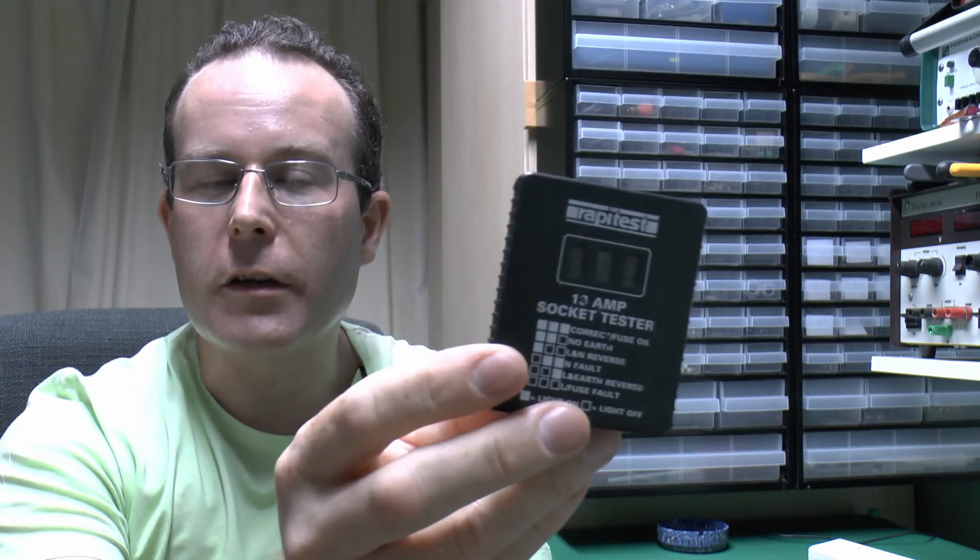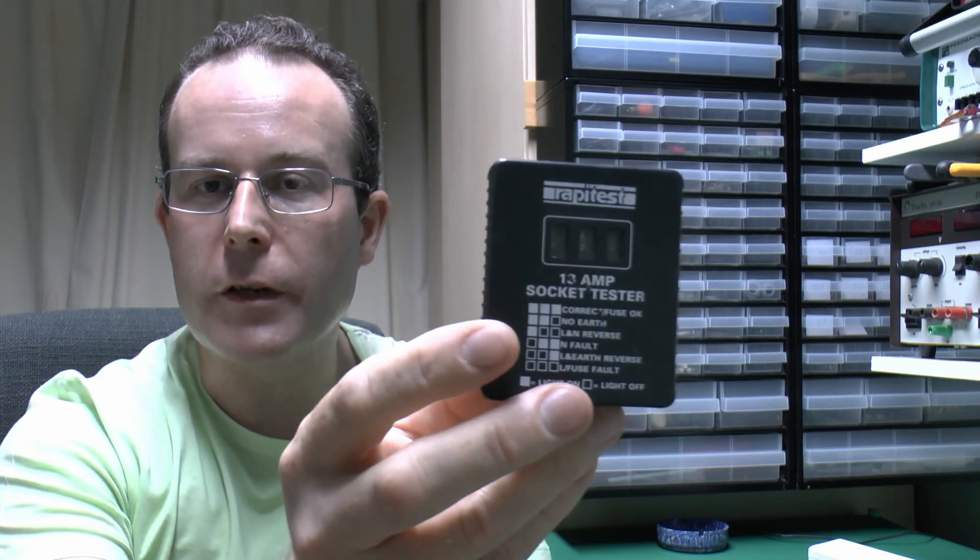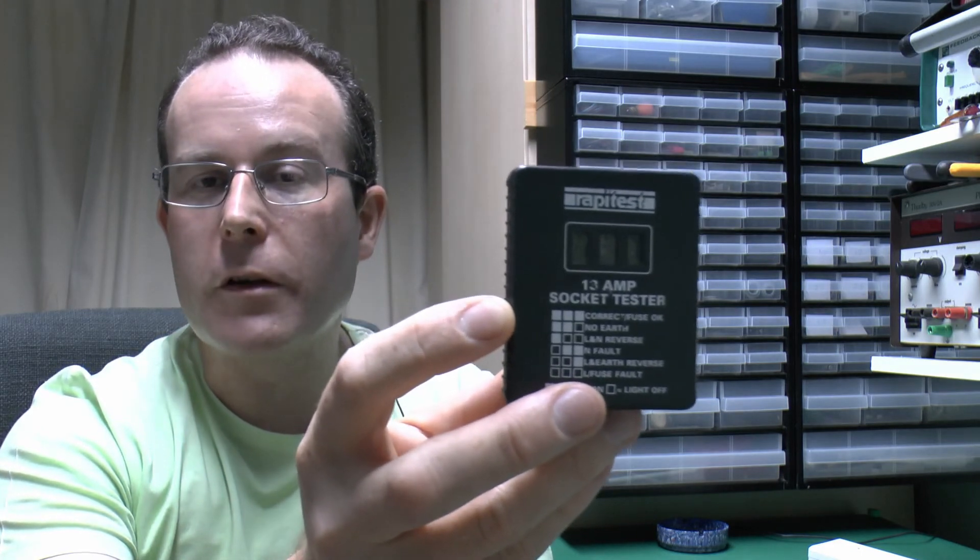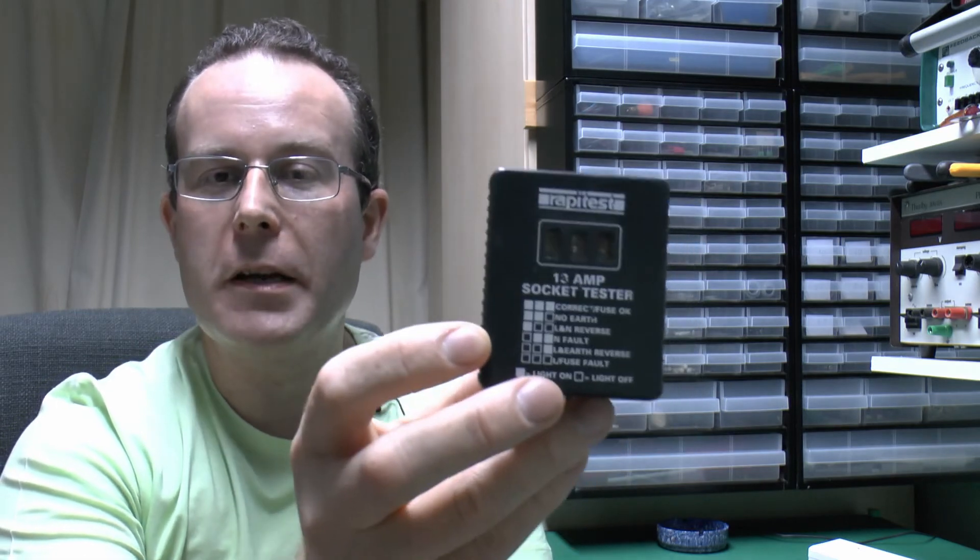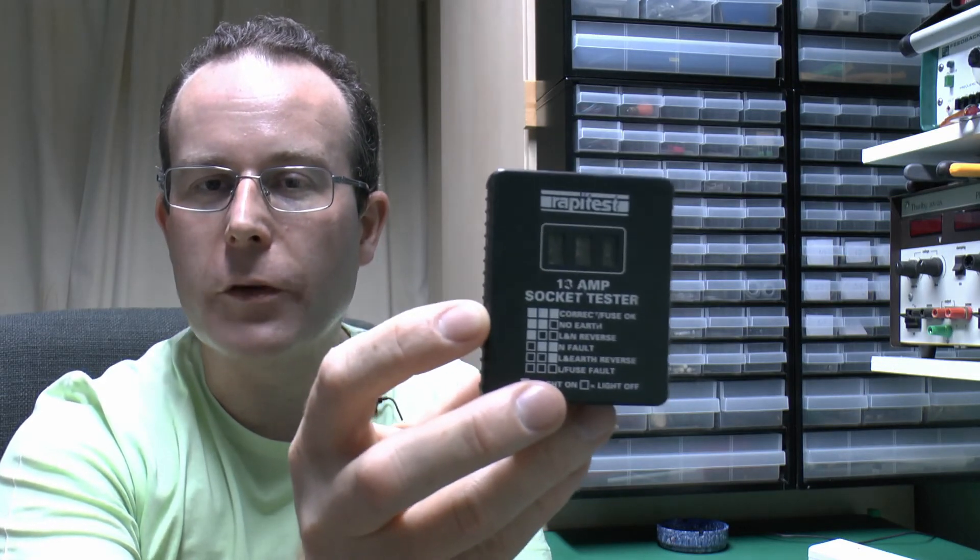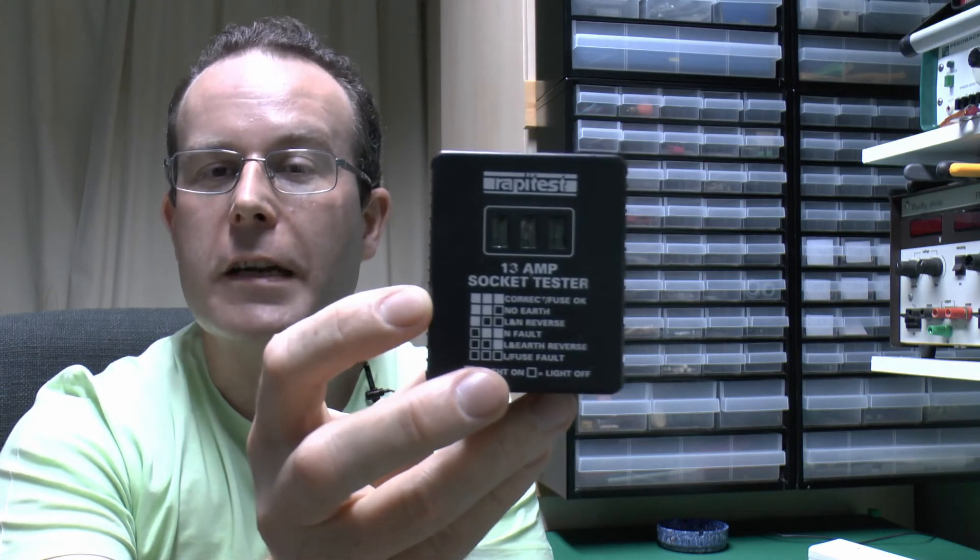So that's the RapiTest socket tester, although all the others of a similar design are going to give the same results. And if you are going to use one of these things, ideally don't because they're not particularly reliable, although if it is the only thing you've got, it's probably better than nothing. Just be aware that if it shows all is well, then it could be, but on the other hand there could be certain other types of faults, as we just saw there, which could result in a dangerous situation.